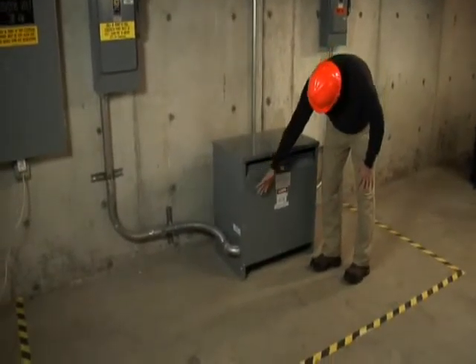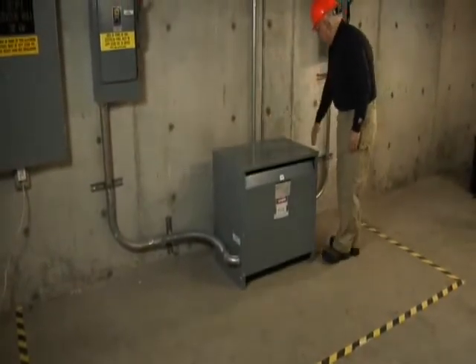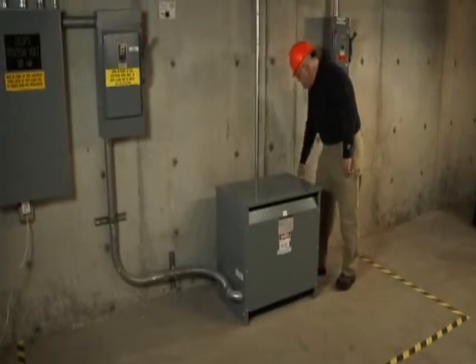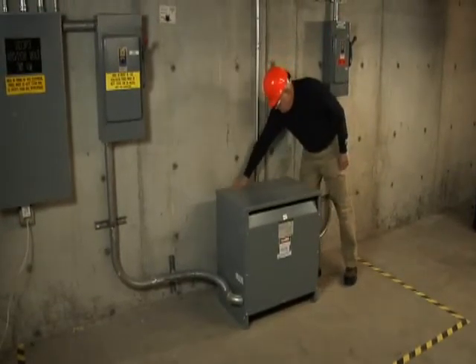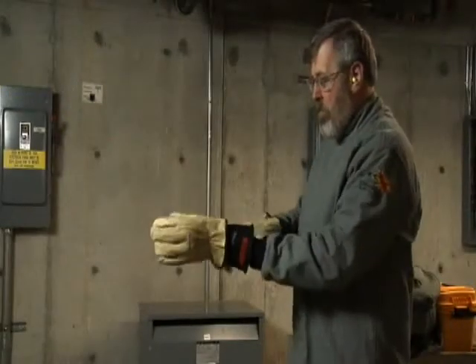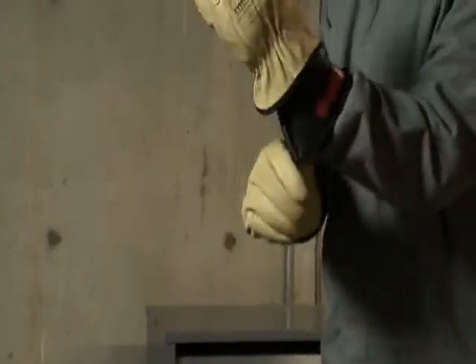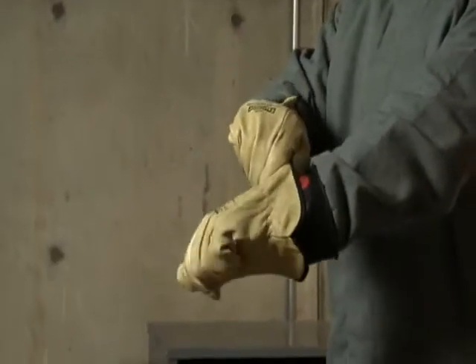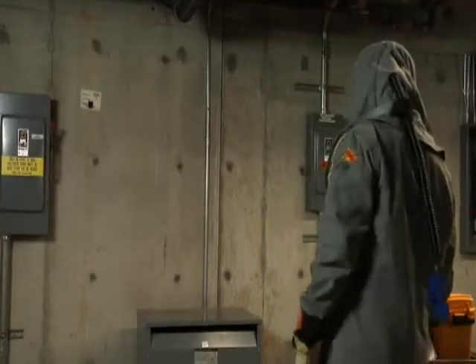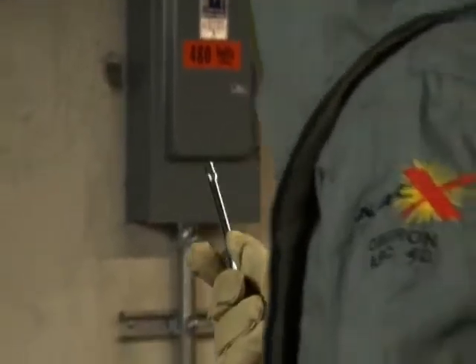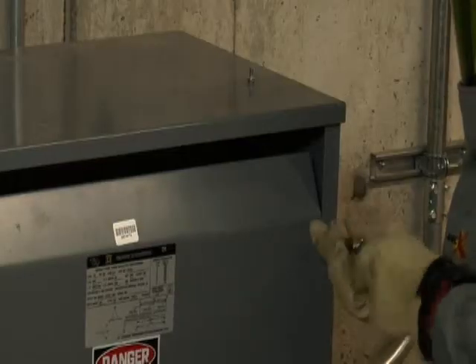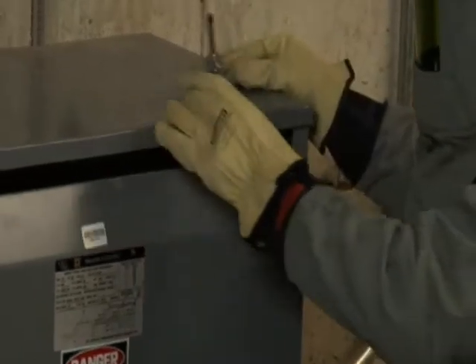If you suspect your transformer is overheating, your next step can be to use your hand to feel the area around the transformer for any signs of excessive heat. It's important to use the proper personal protective equipment, or PPE, when inspecting and testing a transformer. Set up your boundaries and select the appropriate PPE for that category. Listen for any abnormally loud humming or buzzing noises. Be alert for the smell of overheating insulation.